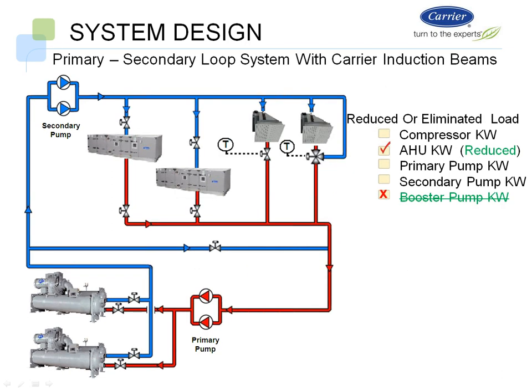So if we take it even one step further and say, okay, let's do a secondary loop with a Carrier induction beam system that's also going to do latent as well as sensible. Now you get to see some more benefits here in your piping, your primary, secondary, because now you can just put your chilled beams in parallel with the air handlers. So from this point, you're running 42 or 45-degree water into your chilled beam, and you're returning it back to your chillers along with your air handlers, and potentially getting a greater delta T across the whole system.